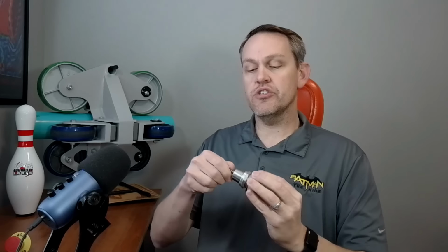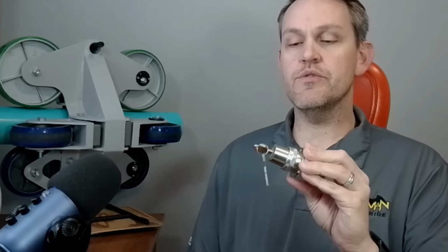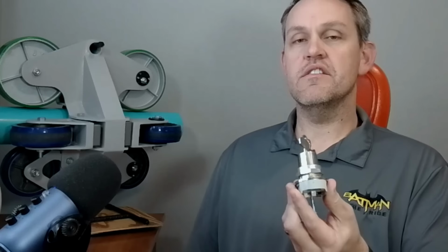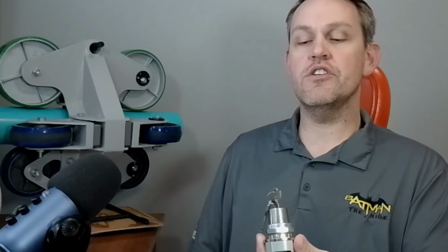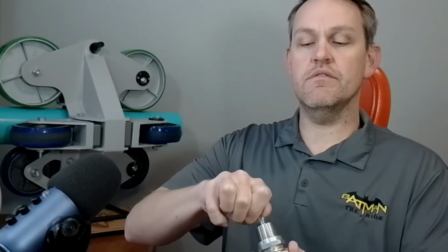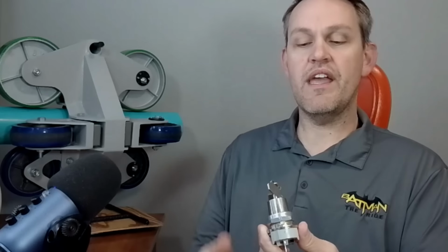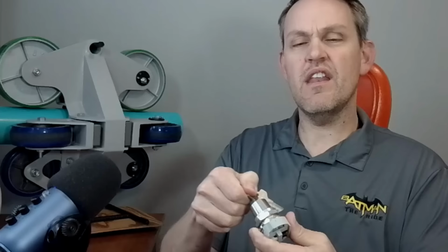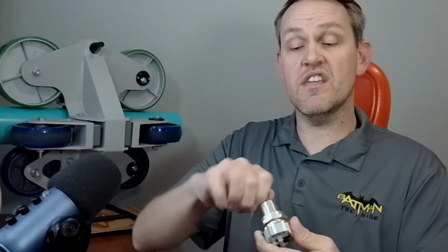The next one, key switches. This is an Allen Bradley 800T key switch. There's the key that goes in it. This is maintained. Two positions. So I can put the key in this position, turn it, it's maintained in that position, and then depending on the key switch, sometimes I can remove the key, sometimes I can't. So where would we use key switches? Well, these are anytime we switch between modes.